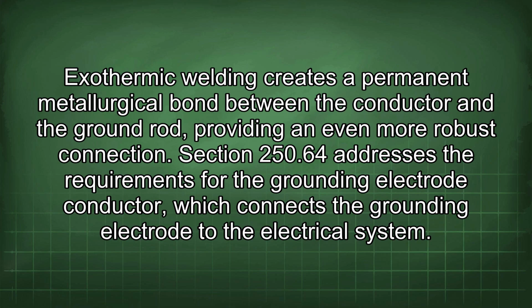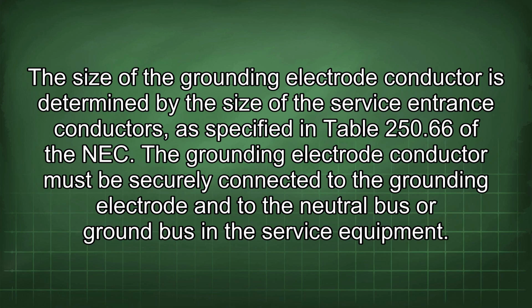Section 250.64 addresses the requirements for the grounding electrode conductor, which connects the grounding electrode to the electrical system. The size of the grounding electrode conductor is determined by the size of the service entrance conductors, as specified in Table 250.66 of the NEC.